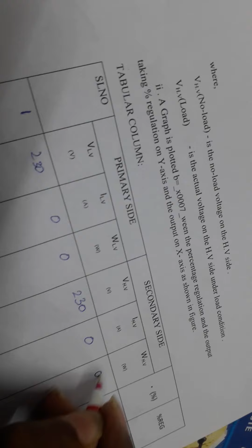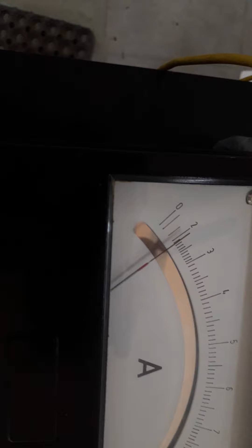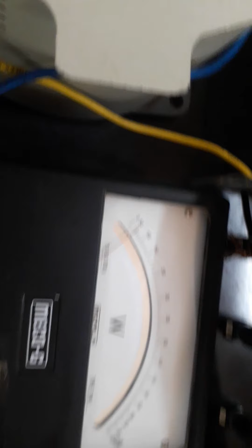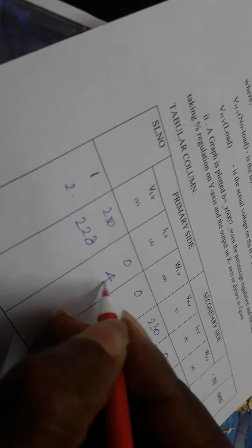Second, I'm going to switch on one load. When we switch on one load, our current increases. How much current is flowing? We have connected at 10 amps, so it is 2 into 2, so 4 amps is flowing. When 4 amps flows, what is our power at the primary? It is 50 on the meter. We have connected it at 300, so it is 50 into 2, so 100 watts is flowing: 100 watts and 4 amps. I will note it down. We have to note down the voltage also. When the load is on, obviously your voltage drops. From 115 it has dropped to 114, so 114 into 2 will be 228 volts. Voltage drops, current increases to 4, and the power is 100 watts.